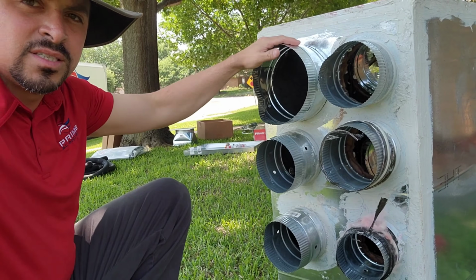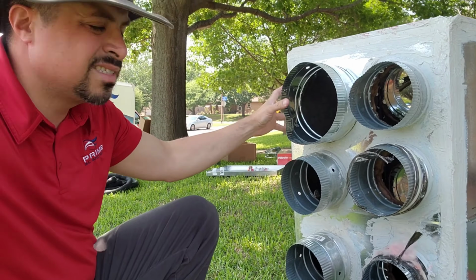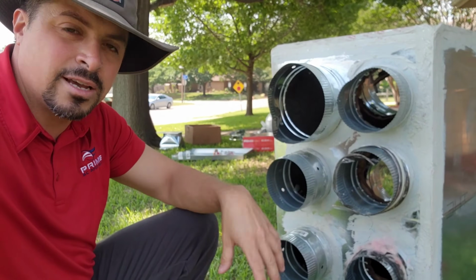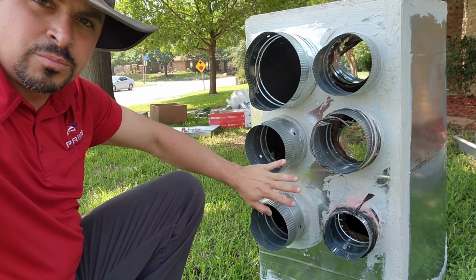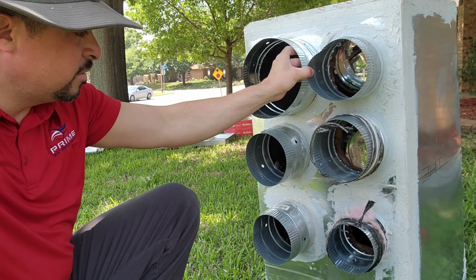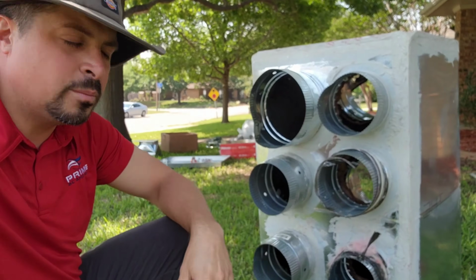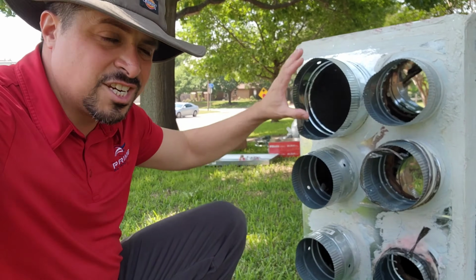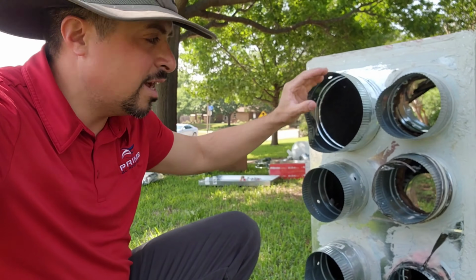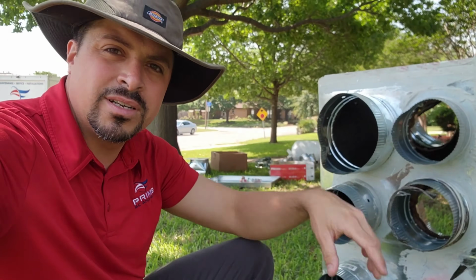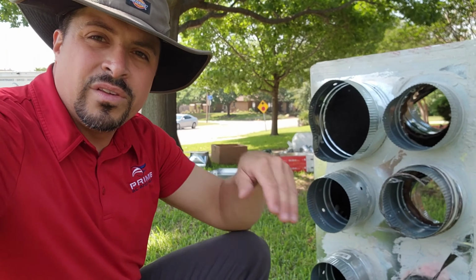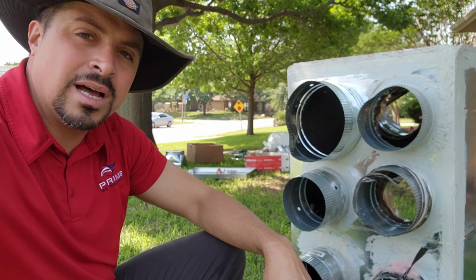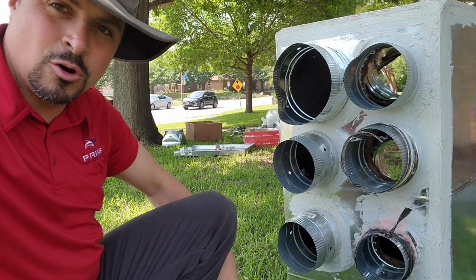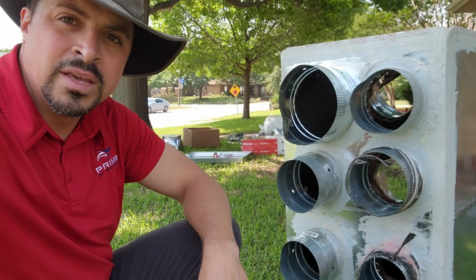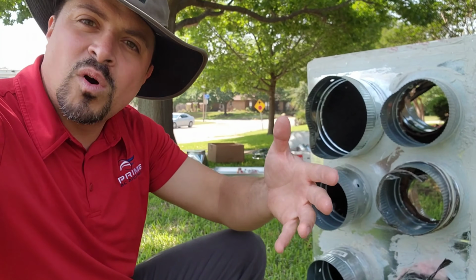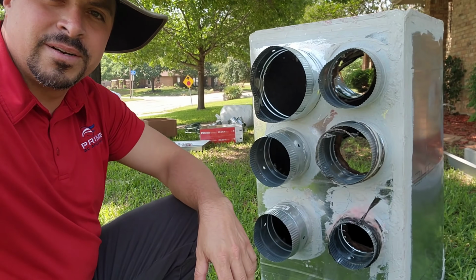Here I want to talk about the supply plenum. This is the box that holds all the air ducts in the attic, and as you can see, it's pretty much a spider of ducts up here - 6 in the front and 4 in the back. What we're going to do differently here is increase the duct size coming out, and then Y off into 2 separate ducts. That's going to help a lot with airflow distribution and keep the home a lot more balanced. So anytime we see home runs, pretty much single ducts all the way through, we definitely want to fix that by putting in Ys to help distribute the airflow a lot better.